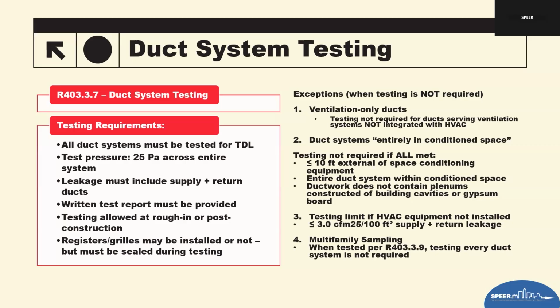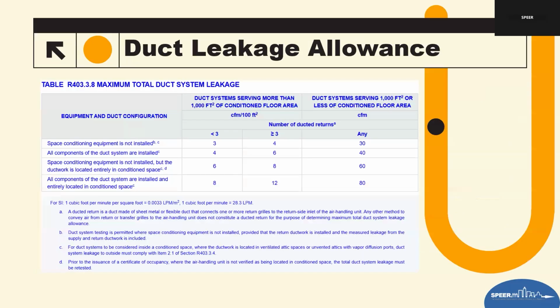We talked about it briefly, but for multifamily there is a sampling protocol. It's not requiring every single test, but it relies on a protocol that we'll see in another slide in just a second. The big takeaway, though, is that the 2024 code makes duct testing clearer, more consistent, and harder to bypass. So if a system isn't truly inside the conditioned space, it's going to be required to meet total duct leakage. It can't do the leakage to outside like we saw earlier. It's going to have to be listed as not 100% inside conditioned space.